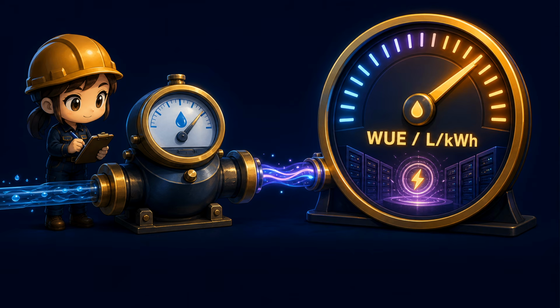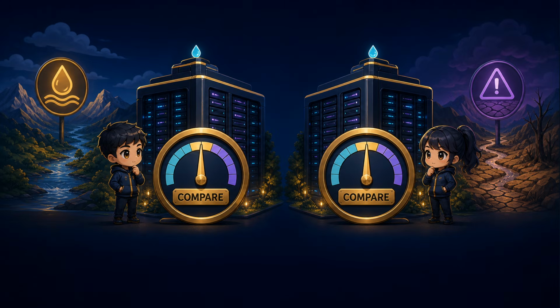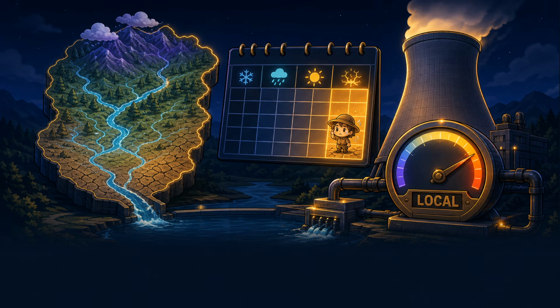A facility-wide metric called water usage effectiveness measures annual site water use in liters per kilowatt-hour of IT energy. It can compare operations with similar boundaries, but it cannot reveal every local consequence. For that, you also need watershed conditions and the timing of demand.